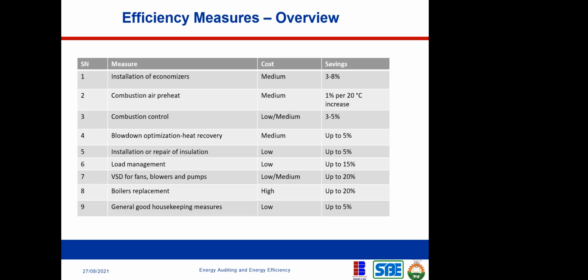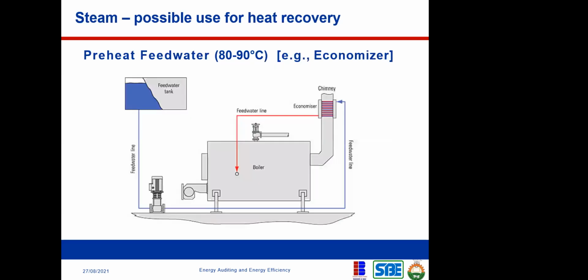Now, an economizer is just something that we'll use to capture the heat in the exhaust gas. Okay, we capture the heat with water. So the exhaust gas, let me show you. Okay, so this is what the economizer is. So this is a boiler. Now this is the exhaust gas, right? So you pass water through this exhaust gas to recover the heat from this exhaust gas.